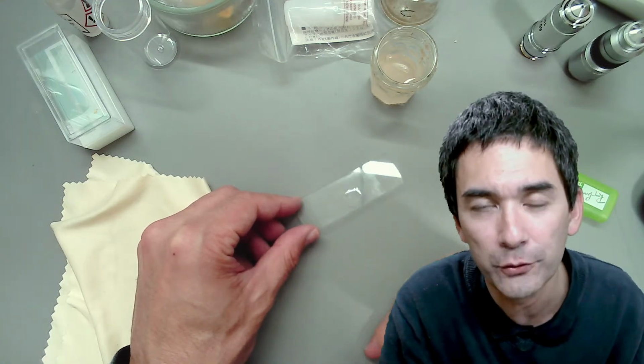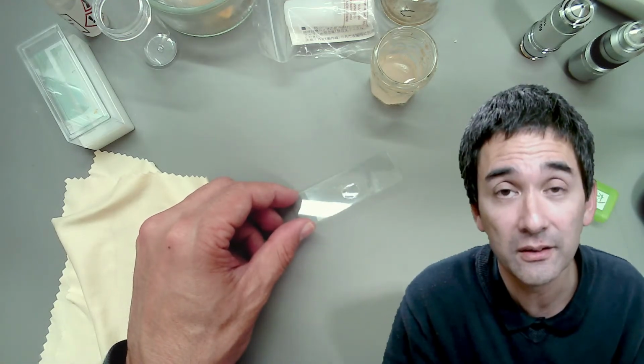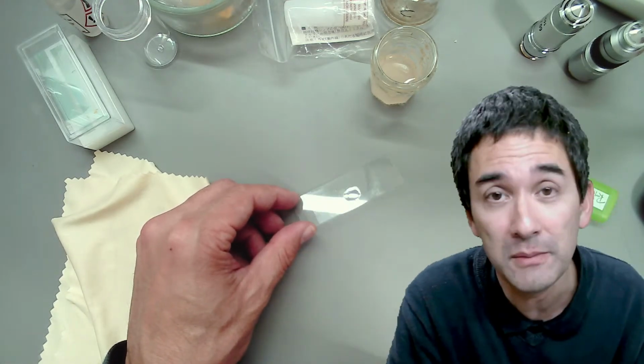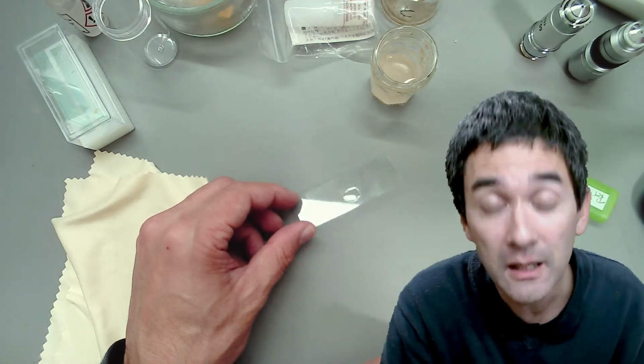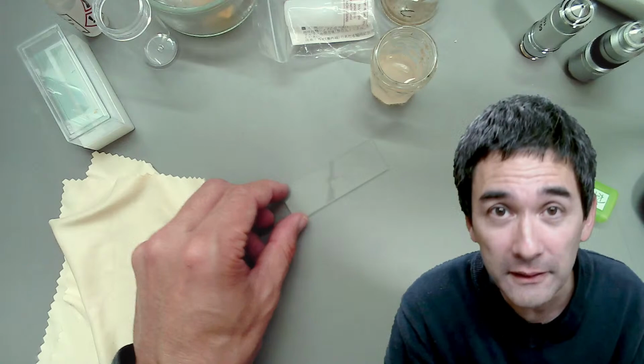I was not patient enough to wait for it to dry, and I rotated the objective directly into the mounting medium. And this is a very fast drying mounting medium. I panicked, but I got it cleaned off completely using an alcohol-ether solution.